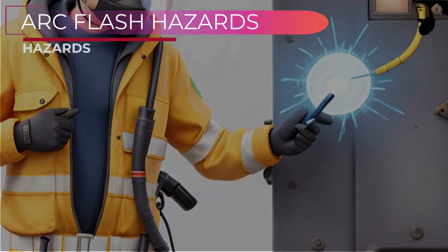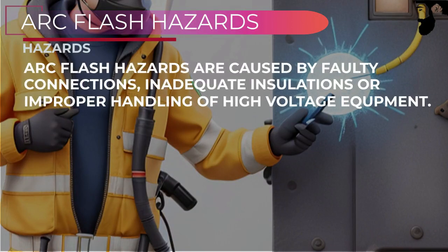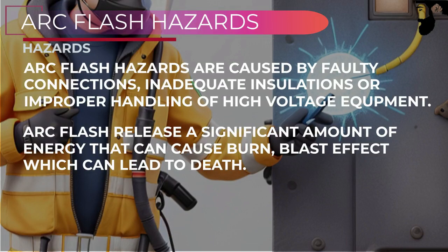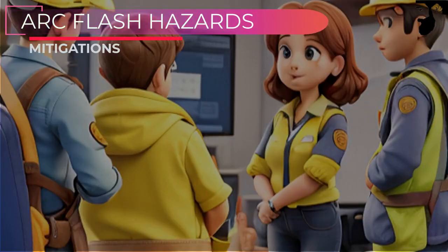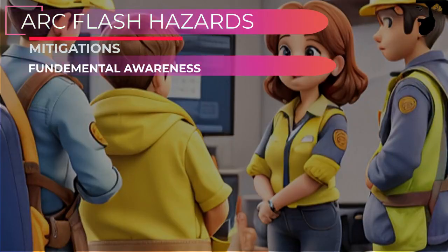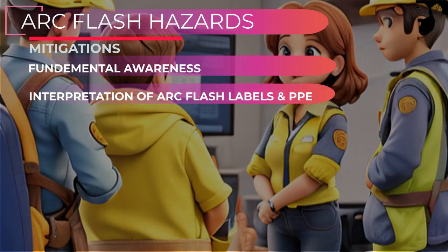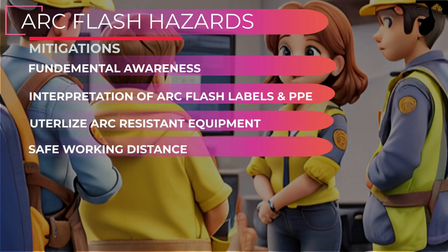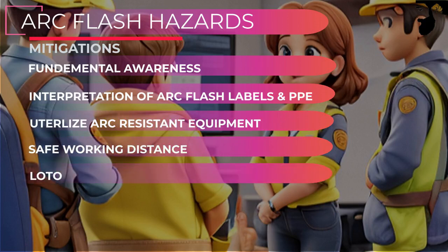Next, ARC flash hazards. Faulty connections, inadequate insulation, or improper handling of high-voltage equipment can all contribute to ARC flash incidents. ARC flashes release a significant amount of energy and could cause burns and blast effects, which can lead to death. Personnel must have a fundamental awareness of ARC flash hazards, incident energy, and ARC flash boundaries, including interpretation of ARC flash labels and PPE requirements. To minimize risks, select and utilize ARC-resistant equipment, maintain safe working distances from exposed electrified items, and apply lockout/tagout methods for ARC flash dangers.